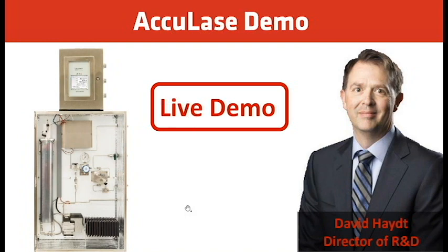Okay. Is there any concern that the target trace gas components are absorbed to the membrane filter? There's always a concern about sample conditioning and maintaining the integrity of your sample. The filter itself, no. There's no concern about losing or absorbing. But when I opened that filter and showed how to change the membrane, you saw that oily stuff in there. And that's what I would be concerned about, is that oily material can certainly cause absorption, especially of H2S. It can absorb into that kind of material, so you can have false lows.